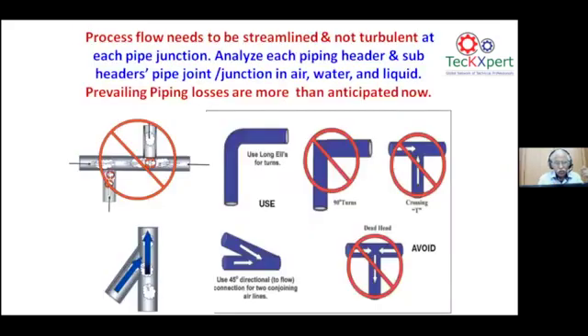What are the do's and don'ts? As a traffic rule, it should be slow in and fast out. So any of the T junctions will never work in the compressed air house or in the system, or any of the process trains on the water line as well. It has to be a conjoining bend or a 45 degrees directional conjoining air line, as we call it, or it can be on pipings. This is like that, and no sharp bends are allowed. Longer bends will definitely reduce the friction loss by around 70%.